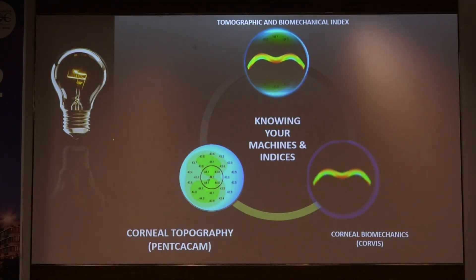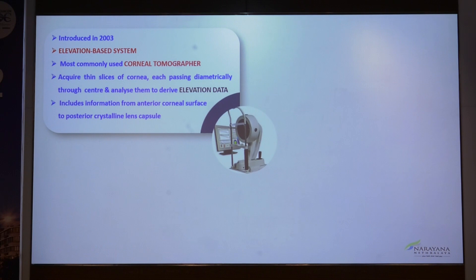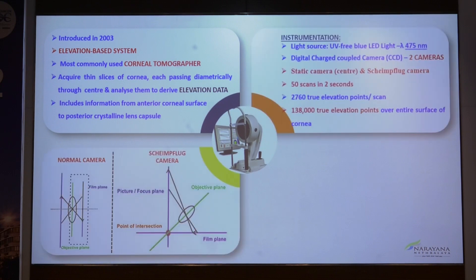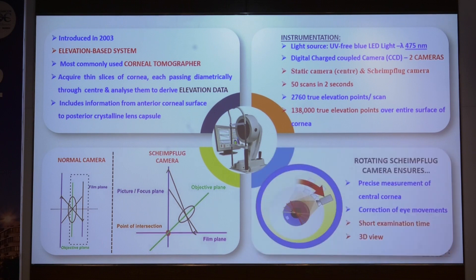Pentacam is an elevation-based system. It's a corneal tomographer based on the Scheimpflug principle. It has two cameras: the static camera which lies in the center, and the Scheimpflug camera which rotates and records 50 scans in 2 seconds, measuring 138,000 true elevation points. The rotating Scheimpflug camera ensures a short examination time and a 3D view.